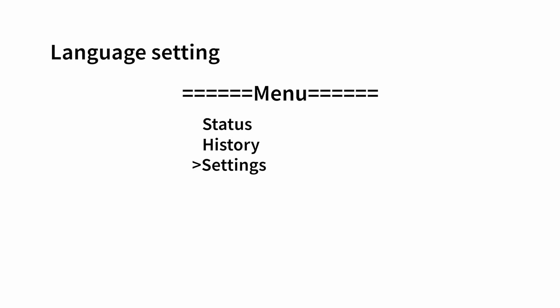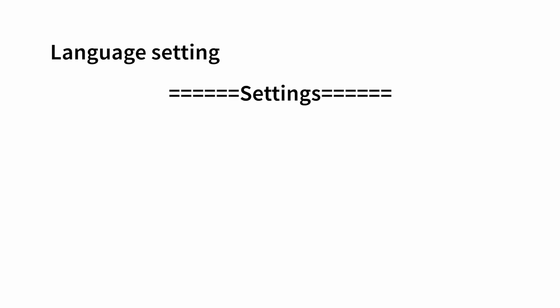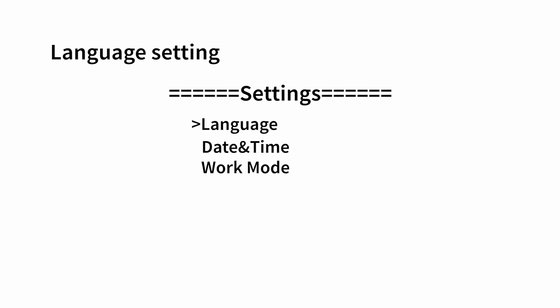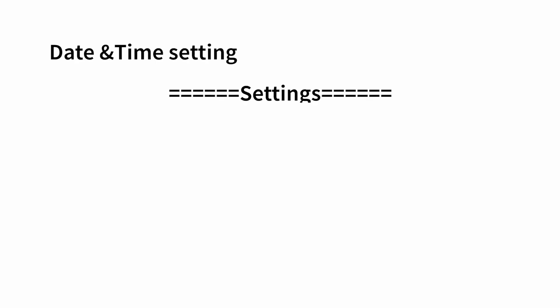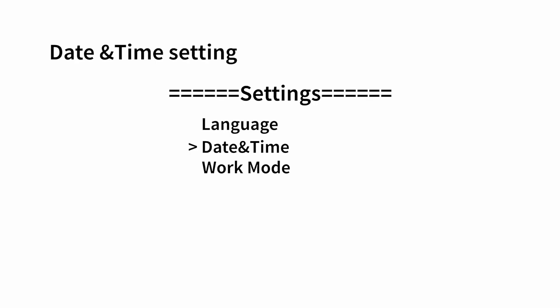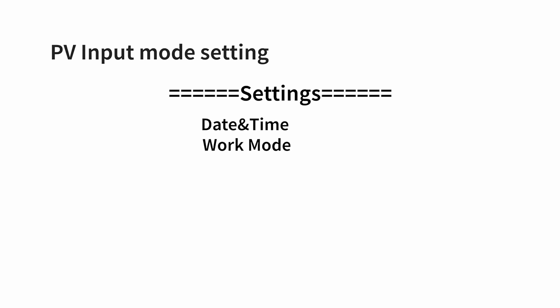Language setting. Press the Enter key to enter the main menu, Settings, Language, and select Language. Long press enter to confirm the setting. Date time setting, select date time to set the time and date of the inverter, long press the enter key to confirm the setting. PV input mode setting, PV, select PV config to set the PV input mode of the inverter, long press the enter key to confirm the setting.